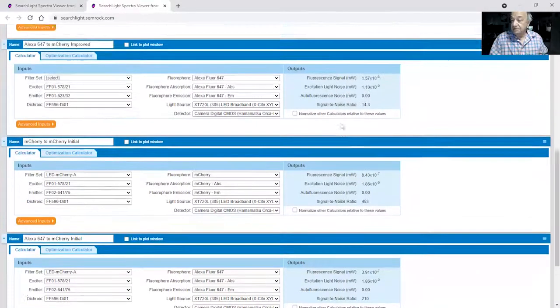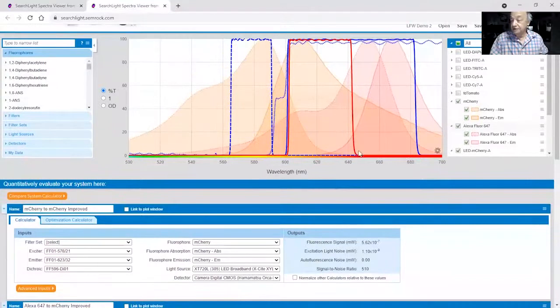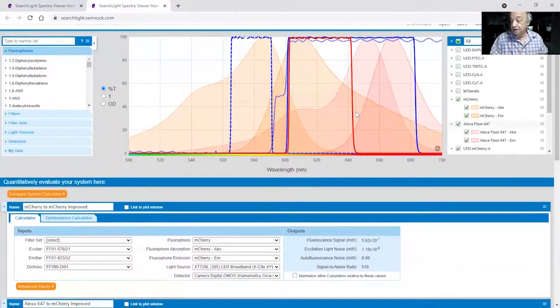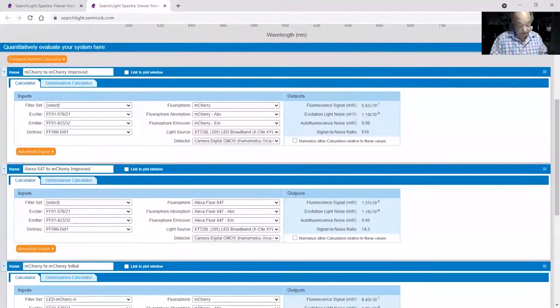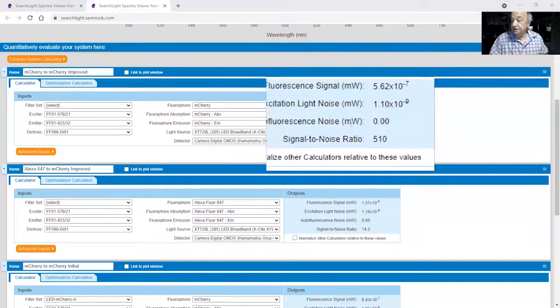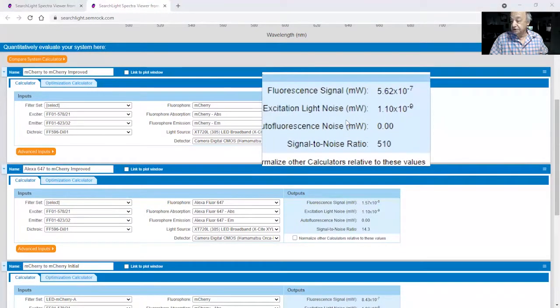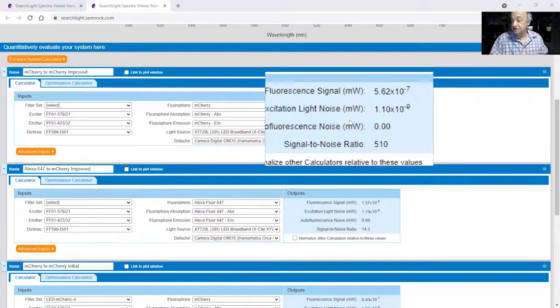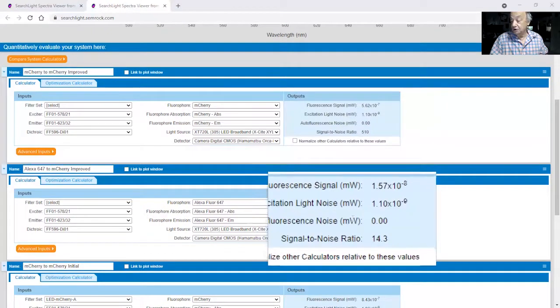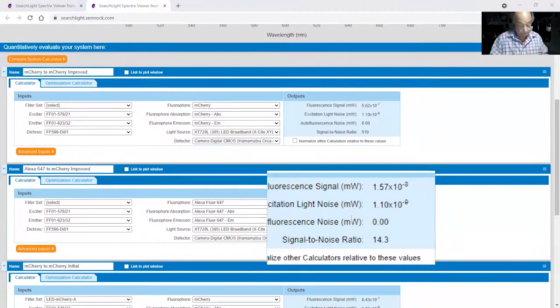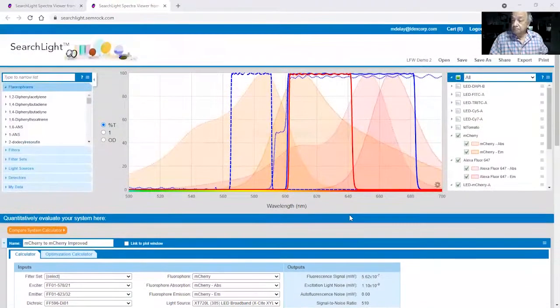So what one has to do then is propose an alternative and prove that it would work. The alternative is to choose a filter like this, which does not extend as far into the red. And so we can now compare and see how the situation is here. And in fact, the fluorescence signal is significantly reduced from 8.4 or so to 5.6. But on the other hand, the crosstalk or bleed through is now very greatly reduced. So this would not be expected to be a major issue at this point. So let me go back to the PowerPoint and continue.